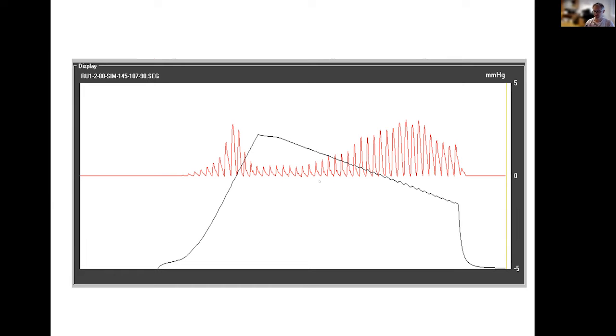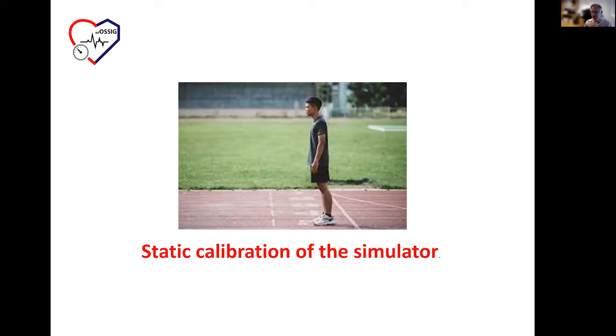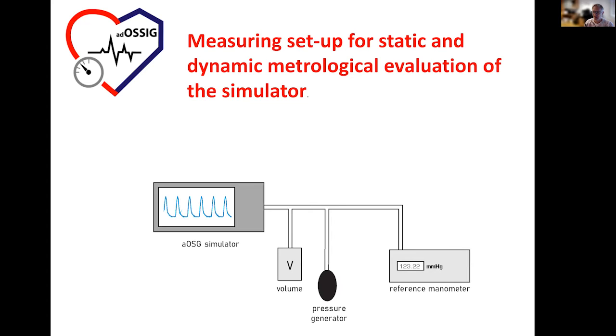If the simulator is an electromechanical device, it should be robustly repeatable, and this is what we tested. So basically, the calibration of a simulator, of any simulator, not only the physiological simulator, which is the result of the adOSSIG project, but also of any other kind of simulators, because there are also commercial simulators available. So basically, we divided the calibration in two parts. One part is the static calibration. And the static calibration just means that we would be testing the simulator's pressure gauge, pressure transducer. This is done in a classical way, like with all manometers, with all pressure measuring devices.